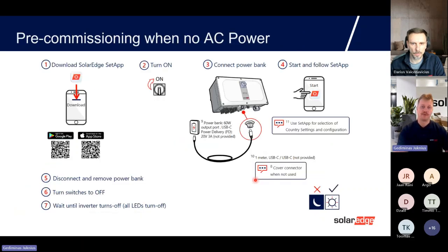One option which is not very popular in the Baltics, but in Western Europe it's more popular, is pre-commissioning without AC power. If you're installing somewhere in an open field, you have no connection so far from the grid operator, and you want to do the commissioning, you only need a power bank to start the inverter. Then the inverter runs from the PV modules, and you can do the pairing, the measurements, the mapping, the full commissioning, and get the commissioning report. Once the grid is ready, someone on the site only needs to turn the AC circuit breakers on. You don't need to go back to the site, and that is how you win time.